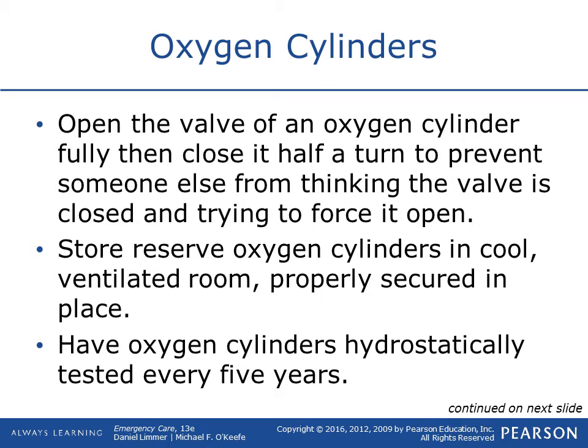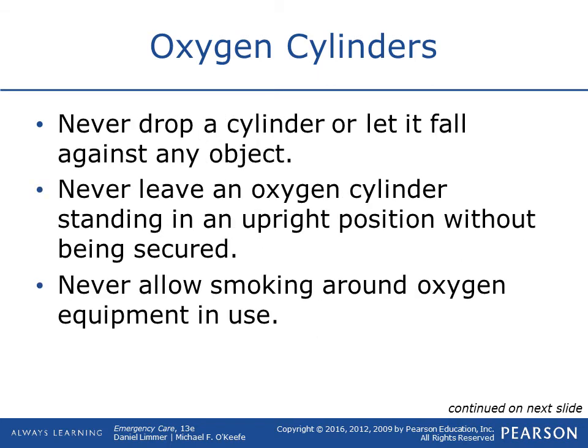The oxygen cylinders, with all OSHA regulations and such, have to be stored in a safe, cool, ventilated area. Since they are under high pressure, you need to be very cautious with them, because if you drop them, they can end up going off like a rocket. If they drop and the top of it breaks off and all that air releases at once, they're just a missile waiting to go. So big cylinders generally need to be stored standing up, locked and chained in, just like in ambulances that are highly secured in there so they don't bang around as the ambulance travels down the road.